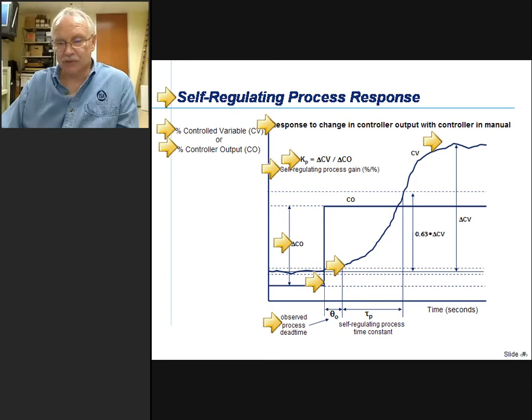And this is the first order approximation of the self-regulating process, which means that we are going to describe the behavior in terms of a single process time constant. Now, the process time constant we start to measure right after the process has started to change, and then we note when it has reached 63% of its final value. Of course, you have to know what the final value is, so you wait till it reaches its final value. At the 63% point is about where the inflection point is, where instead of the slope increasing, it's now decreasing.